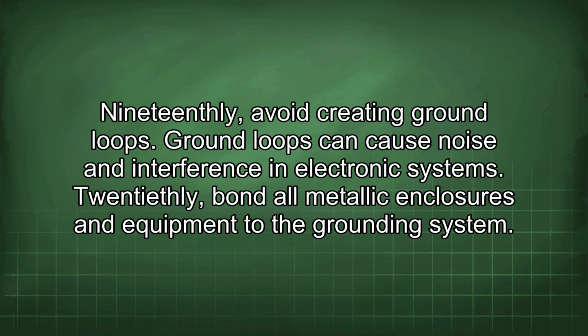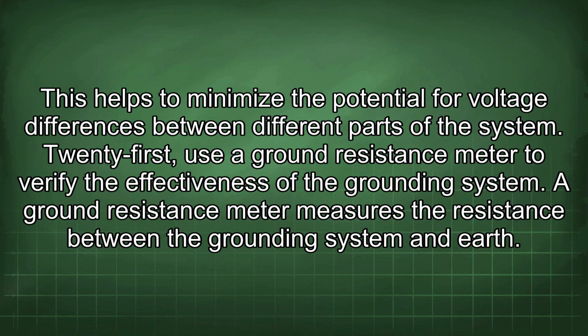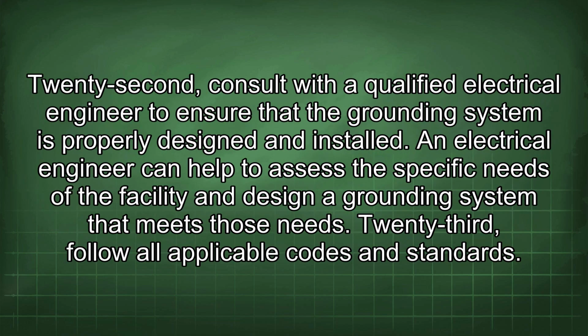20thly, bond all metallic enclosures and equipment to the grounding system. This helps to minimize the potential for voltage differences between different parts of the system. 21st, use a ground resistance meter to verify the effectiveness of the grounding system. A ground resistance meter measures the resistance between the grounding system and earth. 22nd, consult with a qualified electrical engineer to ensure that the grounding system is properly designed and installed.